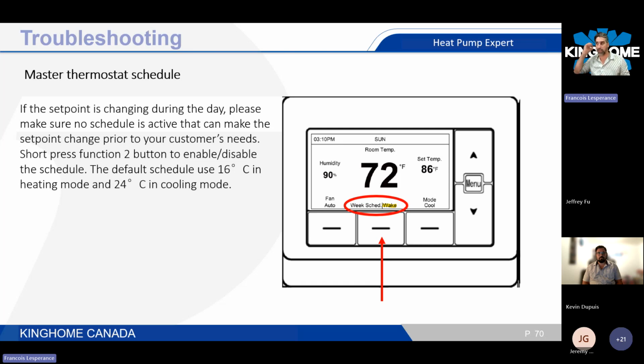So just make sure that you disable this schedule function whenever you are working on it. If you click and hold that function button over here, this writing will disappear, saying that we don't have any schedule active within that white thermostat. So no default schedule active, and you can run the system as usual, like a standard thermostat.